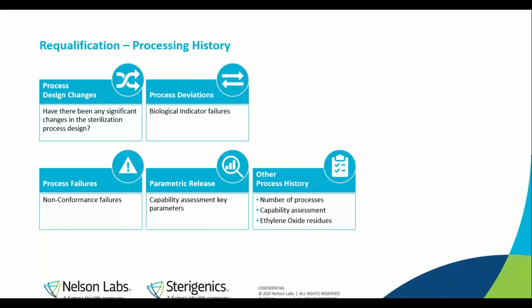Next, we would look at any process failures of the equipment, and if there are any nonconformances noted due to failure or malfunction of the equipment. Next, if the process is a parametric release process, some processes are designed to only look at the parameters and eliminate the BI sterility step, a capability assessment should be performed to evaluate key parameters, specifically the humidity and the EO concentration.